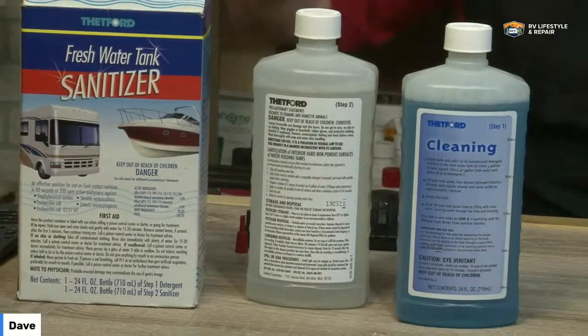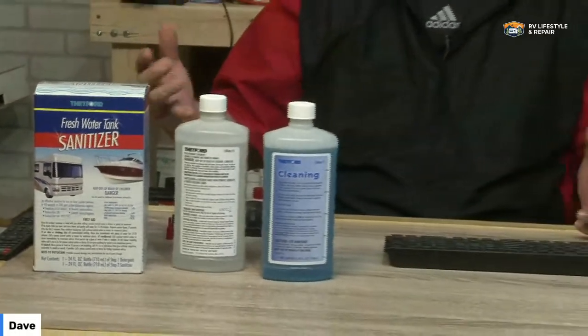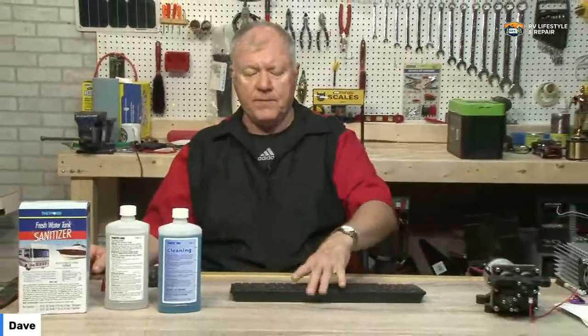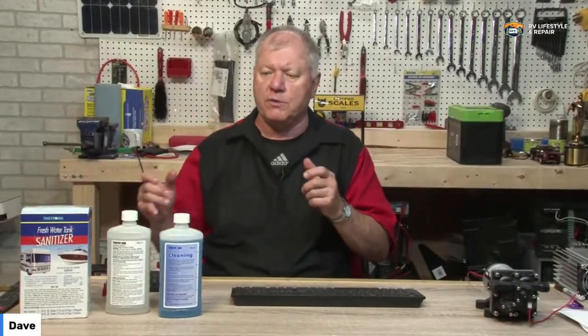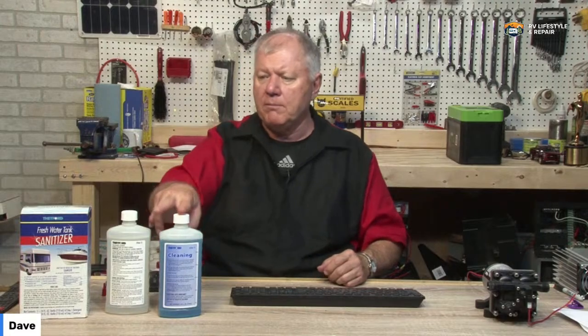For the ice maker, you're going to have to cycle it many, many times. I've had people use bleach — you can put 1/8 cup of bleach in something like a 50-gallon tank, fill it up, and let it sit for a while. The first thing I always do is run it through everything, through all the piping inside, 2 or 3 cycles in your ice maker, then let it sit for 24 hours, go back through, drain the tank out, put in fresh water, and redo that system. Some people don't like the bleach smell, so you can go with a bleach that has more of a flowery or non-chlorine scent. That stuff also works pretty good. Vinegar works, but not quite as well.